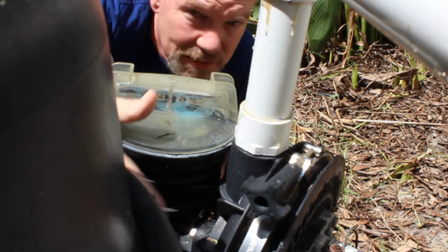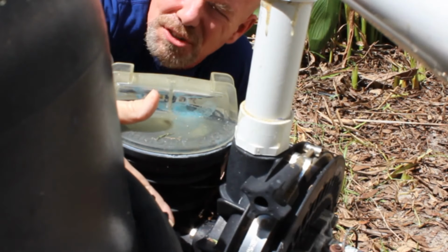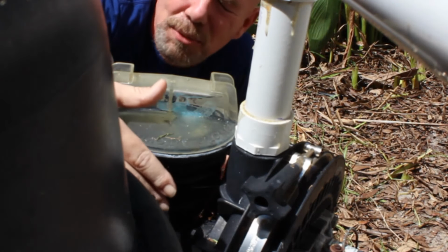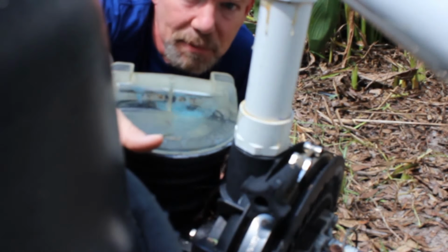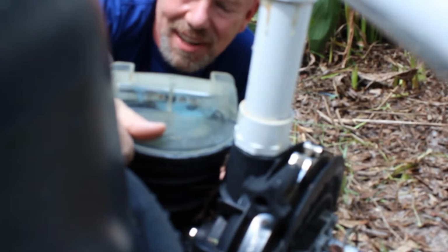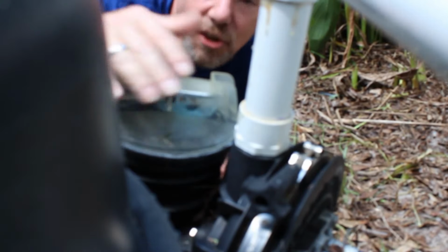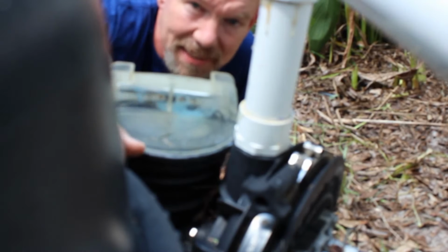If the air bubbles had subsided after a couple of hours, then that would lend more toward a pressure side leak. Pressure side leak will typically only drip water when the pump is running, but once the pump stops, it'll suck in air from wherever that leak was. A suction side leak, now that's only going to draw in air while the pump is running, with one exception, and we'll talk about that too.